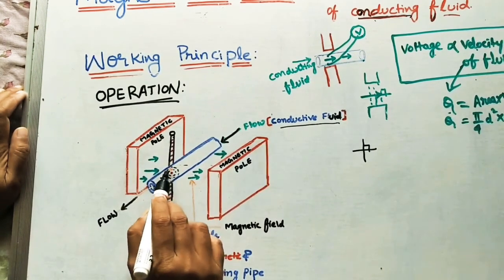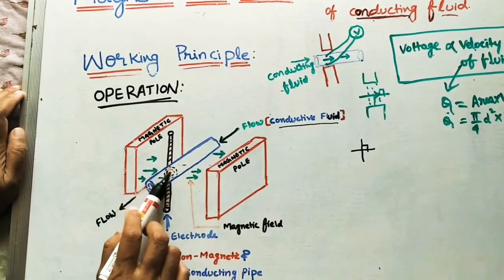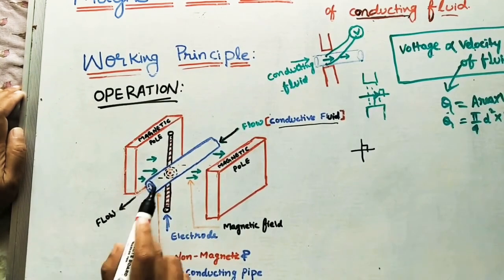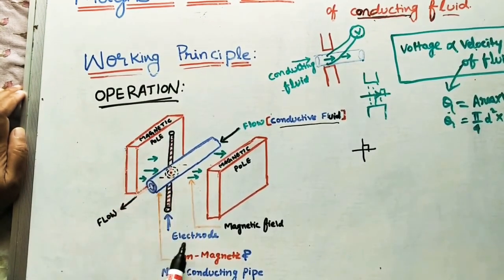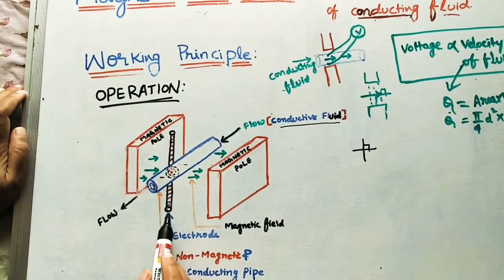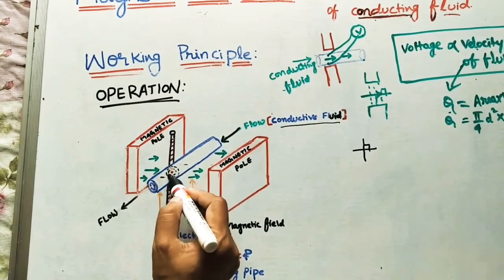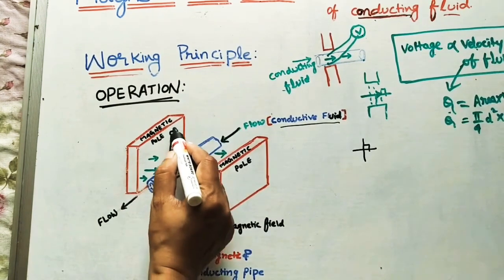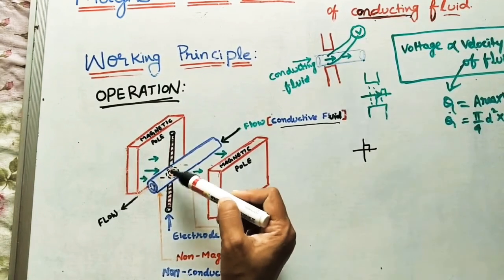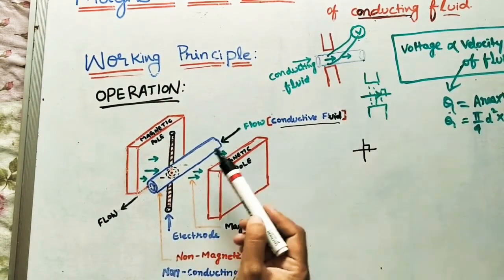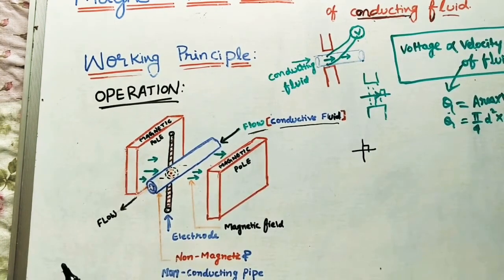Because of this flowing conducting fluid cutting the magnetic field, magnetic field is also present inside the fluid. Whenever the flow comes like this, this flow cuts the magnetic field, and because of it, voltage will generate. That voltage can be found by connecting two electrodes or wires to the pipe and measuring with the voltmeter. Whatever voltage is generated in the fluid, we measure it by connecting two terminals to the voltmeter. This voltage gives the Q value of the flow. This is the main working operation of the magnetic flow meter.